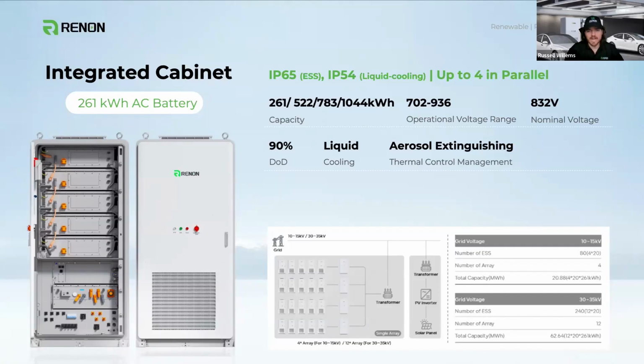These can be run in very high degrees of parallel. Part of the reason this is a good advantage is that if you are doing that AC coupled configuration, you can run multiple arrays of these, four of them in parallel for a megawatt, and then connect those together to create a single array. And then those arrays can then be paralleled together to get over 10, 15, 25 megawatts of power if we really need to. And then that has the ability to step up and really hit those grid voltage or transmission voltage requirements of 10 kilovolts, 35 kilovolts, all the way up to 35 kilovolts if you have enough juice across the board. So really capable system.